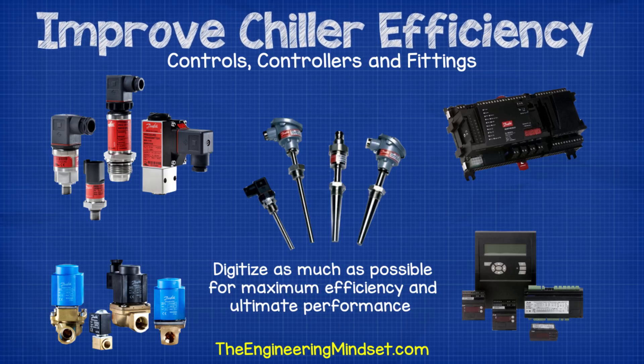Controls, controllers and fittings: where possible, choose digital controllers and sensors as these perform faster and with more precision. When replacing a fitting, check with the manufacturer whether more energy efficient and reliable options are available. Over time manufacturers stop producing parts, making spares harder and more expensive to obtain. Do not just replace like for like — always seek improvement. On the control side, manufacturers often release periodic software updates for controllers and equipment. Make sure your BMS engineer or servicing company is updating your systems where possible. If you use a third party to service your chillers, press them to develop new energy savings control strategies — not just for the chiller but for the entire cooling system.